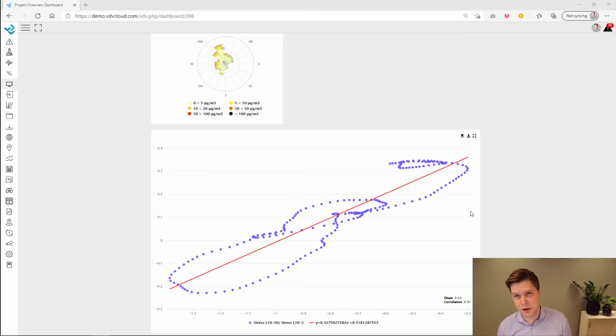So if the sensor reaches limit 1, 2, or 3, then you are doing specific alarms. The bulk alarms are designed where you have a limit, 1, 2, 3, 4, 5 limits, and you are selecting multiple sensors that have that limit. So instead of needing to configure each sensor at a time, you can actually set the limits and choose multiple sensors to have those limits.